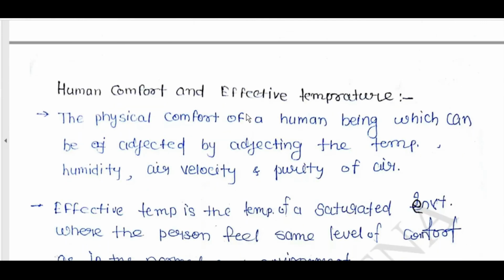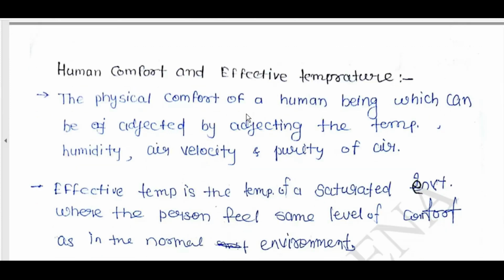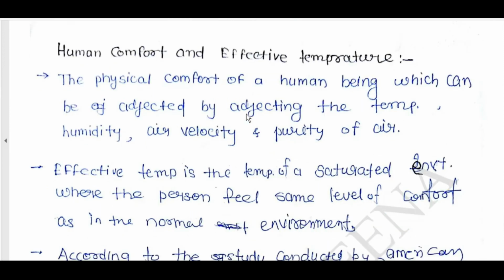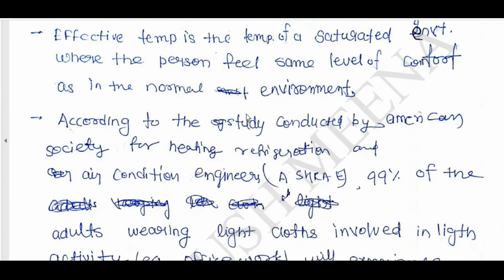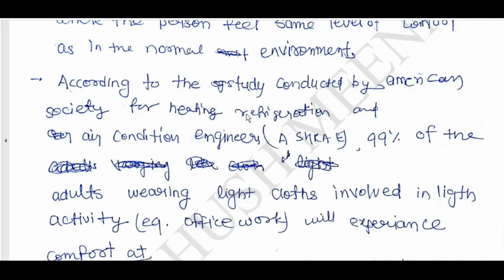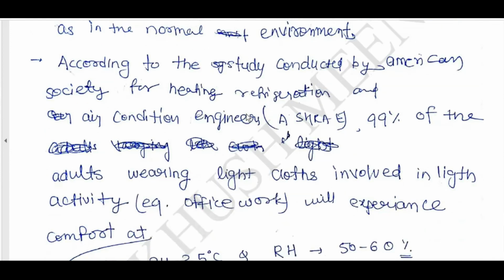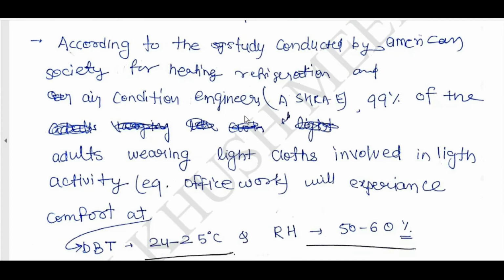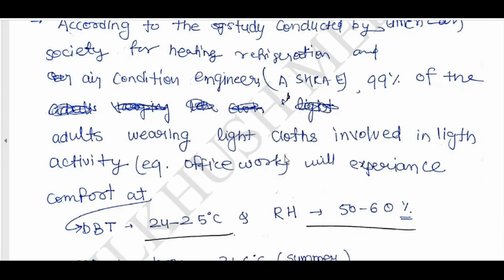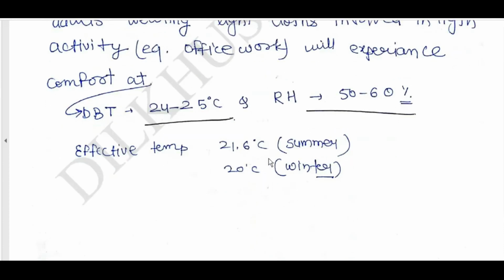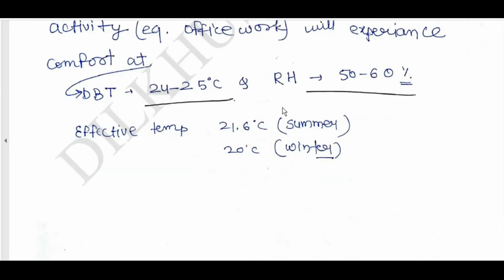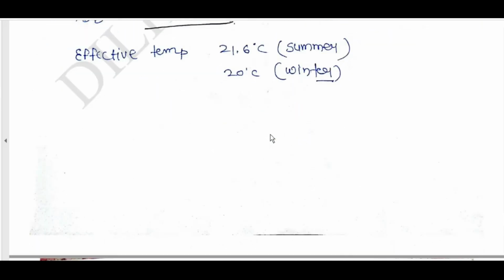Human comfort and effective temperature. The physical comfort of a human being can be adjusted by adjusting the temperature, humidity, air velocity, and purity of air. Effective temperature is the temperature of a saturated environment where the person feels the same level of comfort as in the normal environment. According to a study conducted by the American Society of Heating, Refrigerating and Air-Conditioning Engineers, ASHRAE, 99% of adults wearing light clothes involved in light activity, for example office work, will experience comfort at DBT 24 to 25 degrees centigrade and relative humidity 50 to 60%. Effective temperature is 21.6 degrees centigrade in summer, 20 degrees in winter.